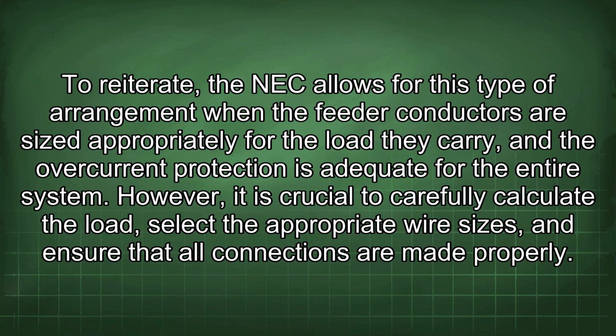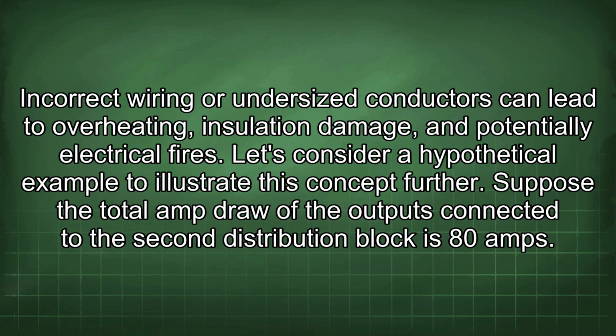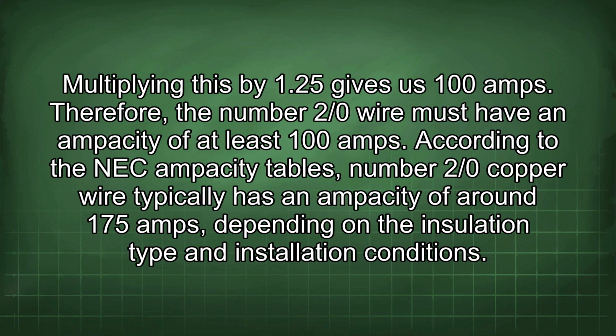However, it is crucial to carefully calculate the load, select the appropriate wire sizes, and ensure that all connections are made properly. Incorrect wiring or undersized conductors can lead to overheating, insulation damage, and potentially electrical fires. Let's consider a hypothetical example to illustrate this concept further. Suppose the total amp draw of the outputs connected to the second distribution block is 80 amps. Multiplying this by 1.25 gives us 100 amps. Therefore, the number 2/0 wire must have an ampacity of at least 100 amps.